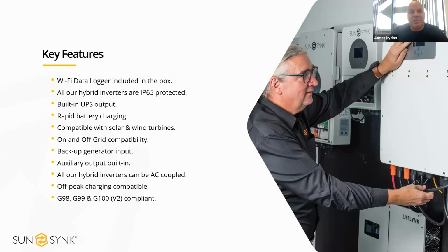So if you've got a 10 kilowatt hybrid inverter with a max potential load of, let's say, 9 kilowatt, what we don't want you to do is install a 10 kVA Jenny, because when that Jenny is running, if the load is 9 kilowatt, we've got no headroom whatsoever to charge the batteries. So it's pointless, really, the Jenny being connected into us. So we would say a minimum of a 15 kVA, even a 20 kVA Jenny. So when that 9 kilowatt load is being satisfied from the Jenny, we've also got the headroom there to be able to charge the batteries at the same time.